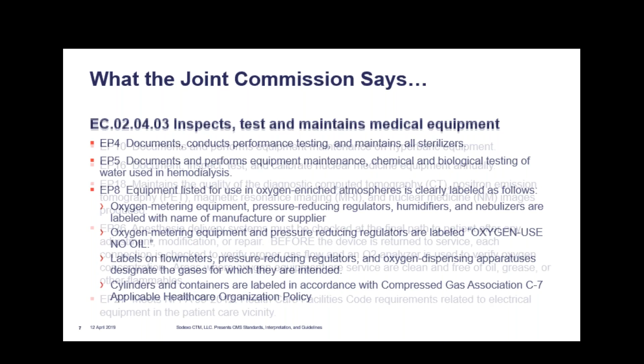This came out last year from the Joint Commission. Before the device is returned to service, each connection needs to be verified for gas flow, and O2 analyzers used to verify oxygen concentration. Areas where oxygen equipment is serviced must be clean, free from oil, grease, and other flammables. Is everybody's biomed shop free of these? Just wondering. I haven't seen one yet.